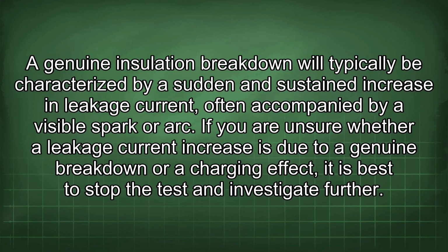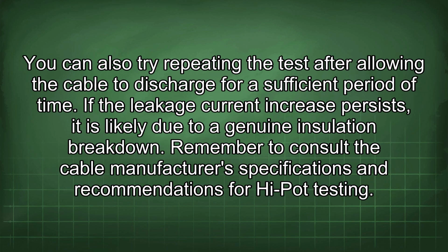A genuine insulation breakdown will typically be characterized by a sudden and sustained increase in leakage current, often accompanied by a visible spark or arc. If you are unsure whether a leakage current increase is due to a genuine breakdown or a charging effect, it is best to stop the test and investigate further. You can also try repeating the test after allowing the cable to discharge for a sufficient period of time. If the leakage current increase persists, it is likely due to a genuine insulation breakdown.